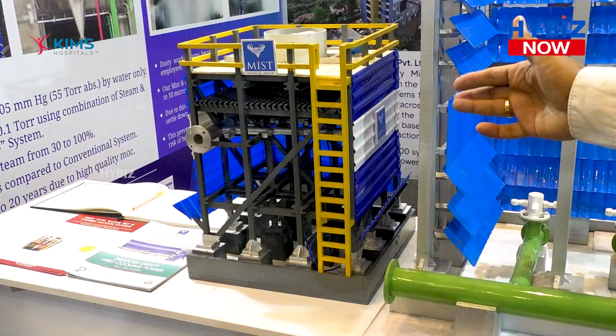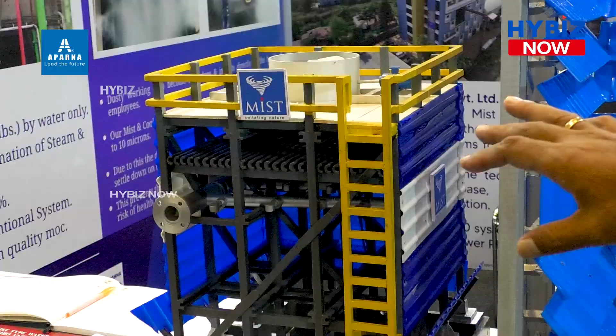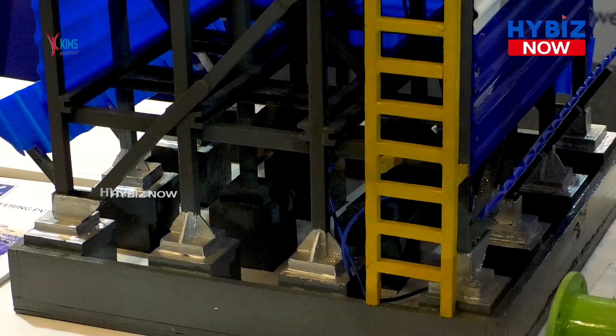Generally, in conventional cooling towers, fills are required, which are installed just below the nozzles because the water particles are not broken below 2 mm or 5 mm size. Therefore, they want water to remain in the cooling tower for a longer period of time. Therefore, they have fills. As we are breaking water particles to 5 micron size, we are exposing large surface area of water particles, and therefore no fills are required.